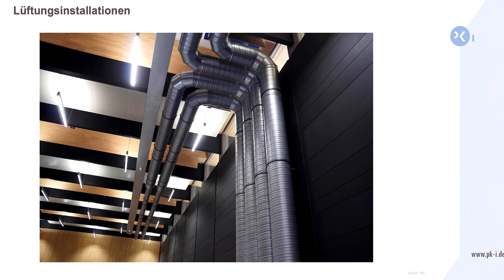When it comes to ventilation, it is important that you convey air in an efficient manner. We want the velocity of air in the ducts to be low in order to minimize electricity consumption. So it makes sense to convey the air efficiently, which at the same time enables heat recovery. Warm air from the building is used again to preheat the cold air supplied from the outside. These are all important aspects when designing a plus energy building.